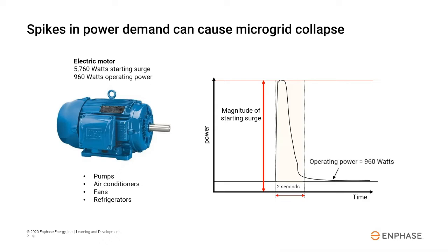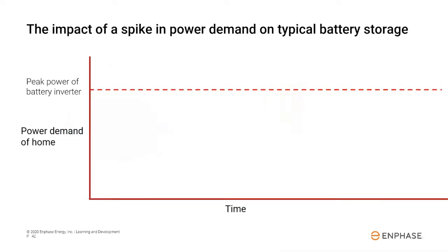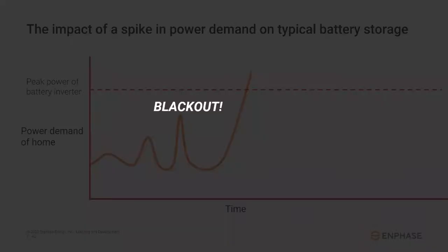In this example, the motor's normal operating power is 960 watts. But when it first starts up, it uses 5,760 watts, about 6 times more power for a second or two. Let's look at what would happen if there was a demand spike without PowerStart technology. The dotted line represents the maximum peak power output of the inverter of the battery system. Normally, the instant the demand exceeds the capacity of the inverters, the microgrid collapses and the customer experiences a blackout.